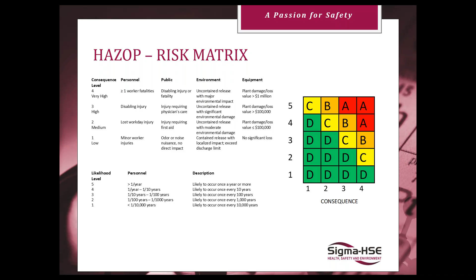All right, so deviation is a combination of your parameter and a guide word. So for flow, it's a pretty common parameter. You'll have, what happens if you have a high flow scenario? You're supposed to be sending 3 gallons per minute of this chemical into the process. You were to change out a pump, and all of a sudden you're pumping out 15 gallons per minute. Less flow if you were to have an obstruction in your line, and now instead of sending that 3 gallons, you're sending 1 gallon. No flow if a valve were to fail closed or a pump were to be shut off and you no longer have a flow.